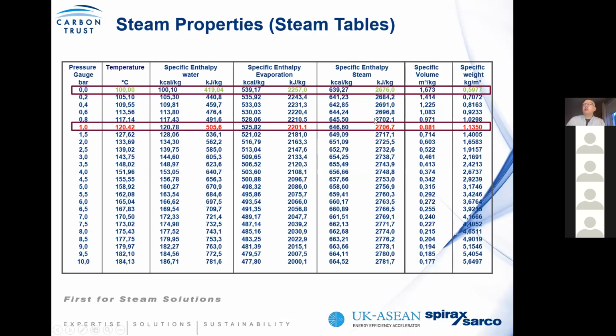And you can see that although the total enthalpy of steam has increased, it's not a significant step change. So in other words, when you look at the total enthalpy of steam, it doesn't change much from one pressure to another. The biggest differences are the temperature required to boil water and the enthalpy of water required to bring it to boiling. However, more specifically, when we look at the specific volume, you can see that as we increase the temperature, the volume reduces. And this has a big significant impact on the ability of steam distribution systems to carry steam to end users. And we will go into a bit more detail on this in a minute.